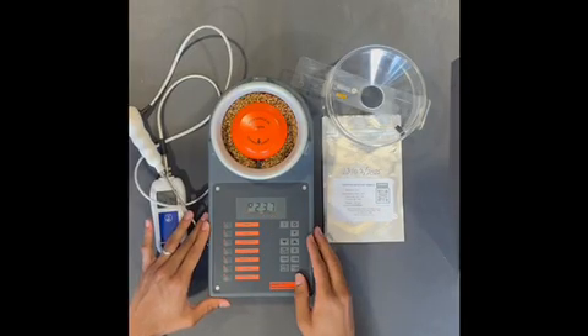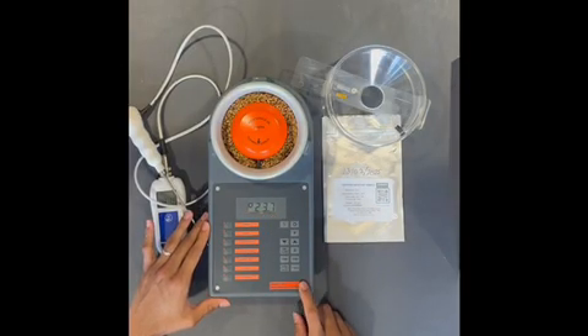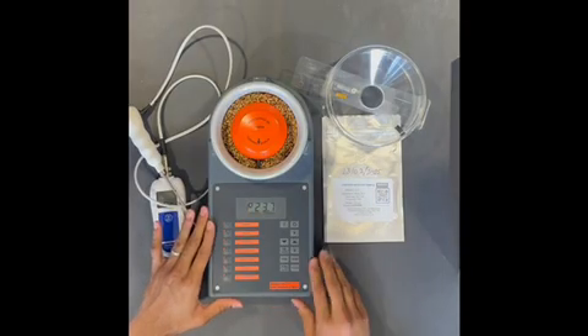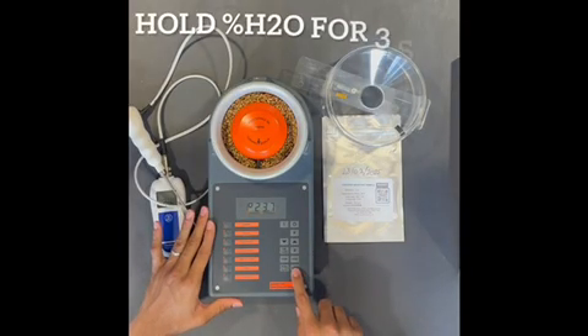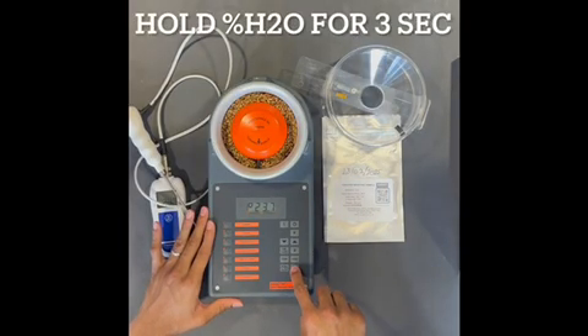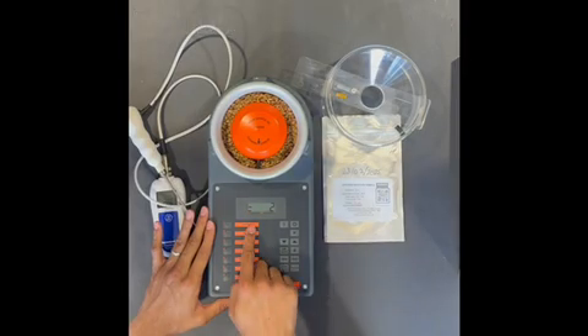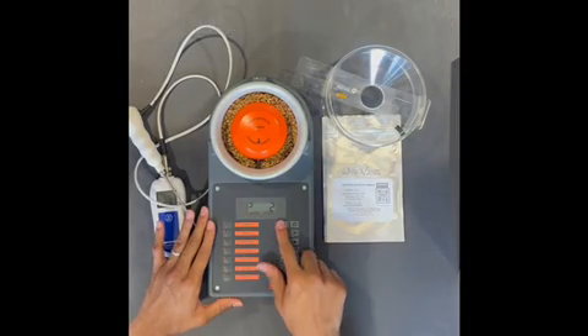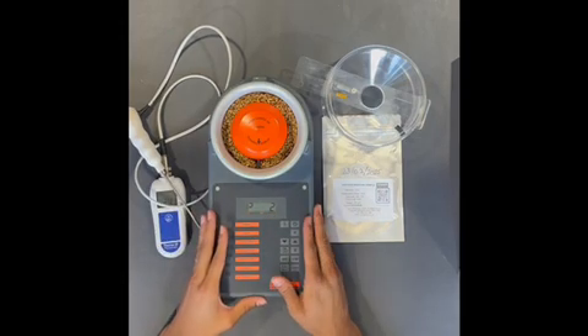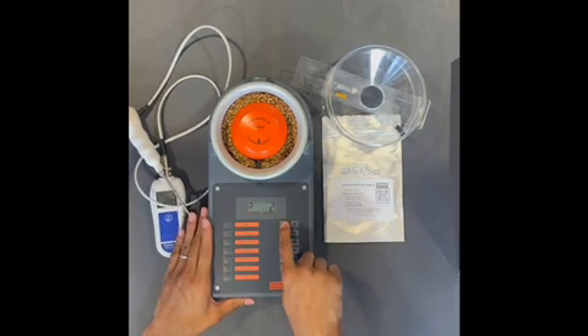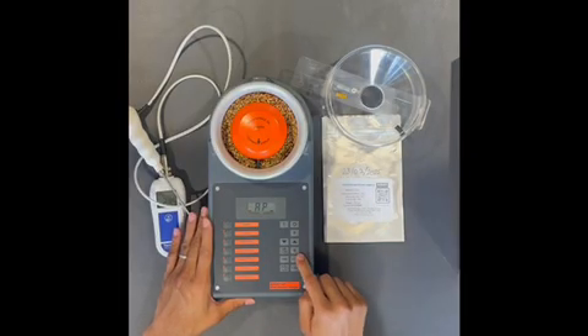At this stage, we've run through the full calibration side of things, and so we want to make sure that the machine knows where we're at. So we'll go ahead and hold down H2O for 3 seconds until we get an upside down C and a number 2. At this stage, we've completed calibration.